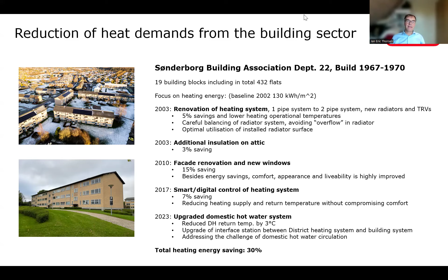And the last one was upgrading the domestic hot water system. In the traditional systems, the domestic hot water circulation can be a challenge, but here we managed to, so to speak, aftercool a higher temperature used for the domestic hot water circulation into the radiators, and we reduced the return temperature by 3 degrees. And you might say that 3 degrees is not a lot, but actually it matters a lot in the big picture. So a total heating energy saving of 30% was achieved. But just to say, digital control and renovating the heating system mean a lot on top of the more building envelope related things.